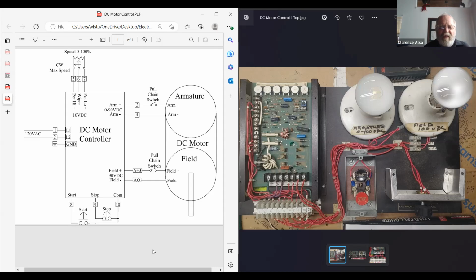As long as you've got the input of 120 volts there, you'll always have 90 volts DC coming out of there. But the other winding, the armature, changes from being off altogether to some voltage between 0 and 90. So you vary the voltage to that, and you get a variable DC coming out of that DC motor control, 0 to 90. So if you want half speed, you get about 45 volts sent out. Full speed sends about 90. That's what it takes to get that thing to turn at specific speeds.